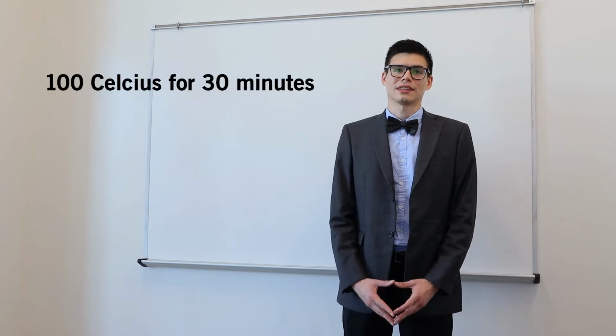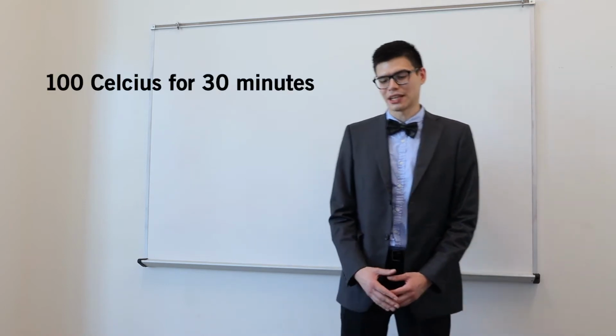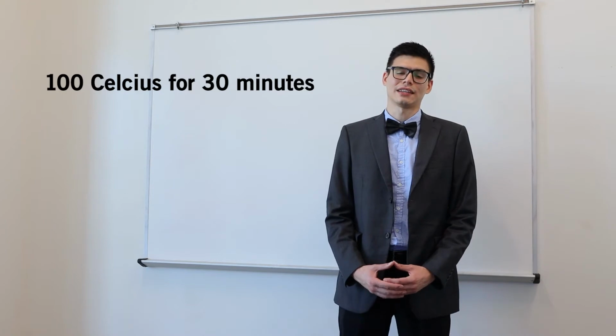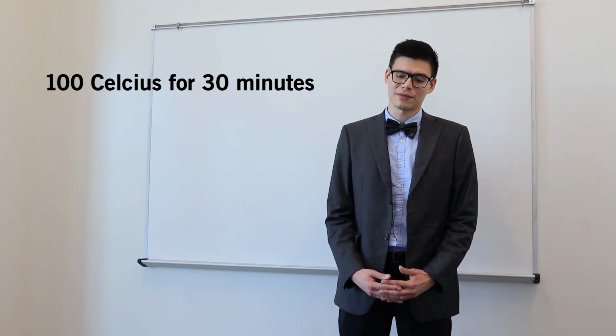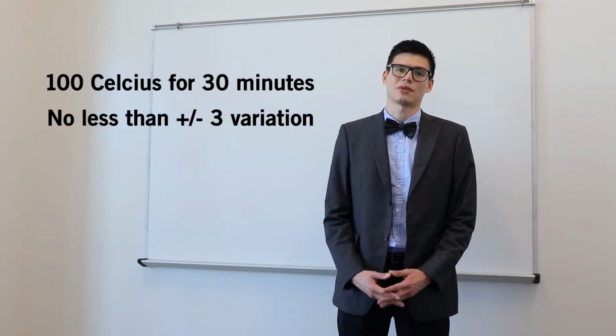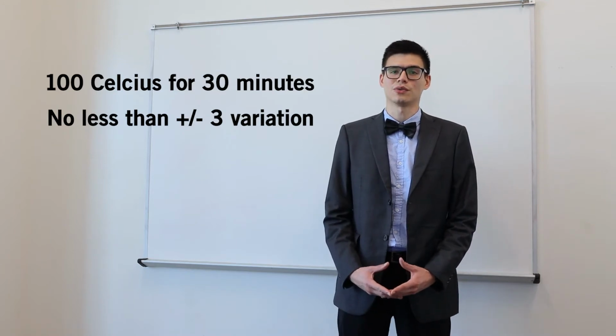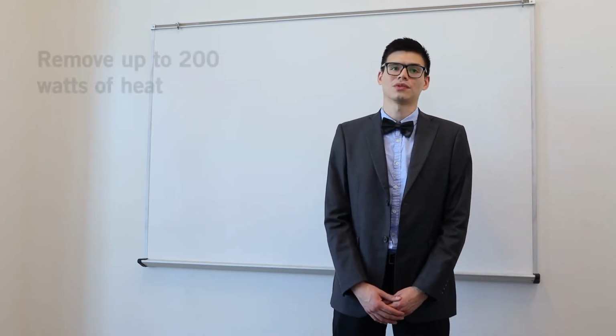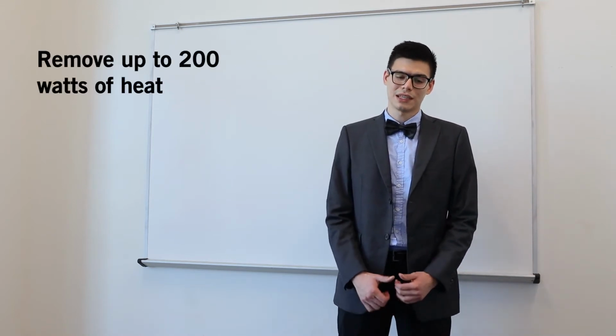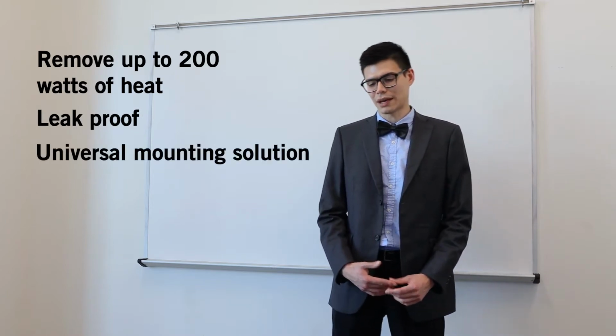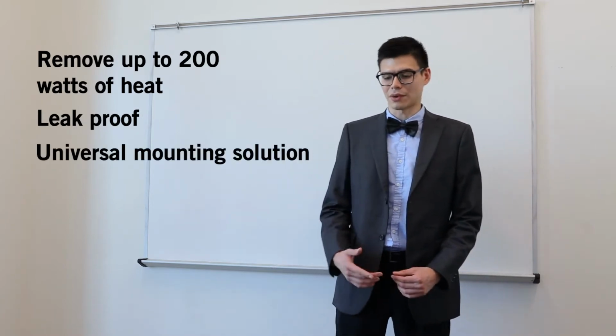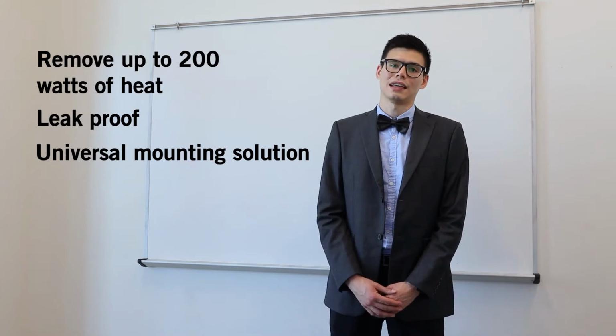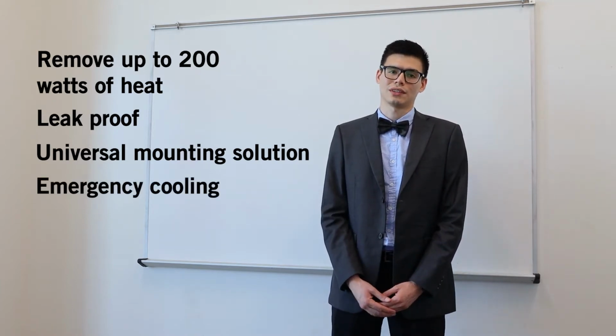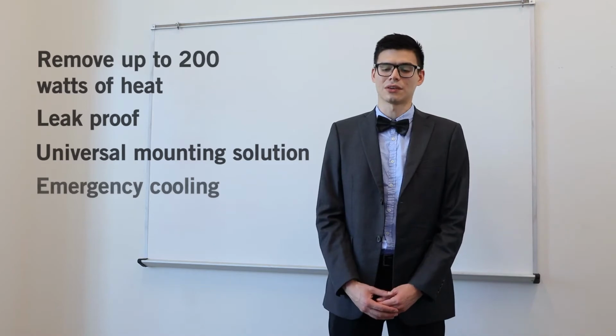For the specifications and functional requirements of our project, we must be able to maintain the power module at 100 degrees centigrade, and this needs to last for 30 minutes, and the variation of temperature cannot be more than 3 degrees Celsius. And this is according to UL testing standards. Our thermal test system must be able to remove 200 watts of heat. It must be leak-proof. It must have universal mounting for different power modules that they will be testing. And it also needs an emergency kill switch, which will also activate emergency cooling.